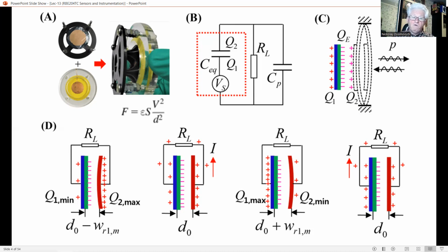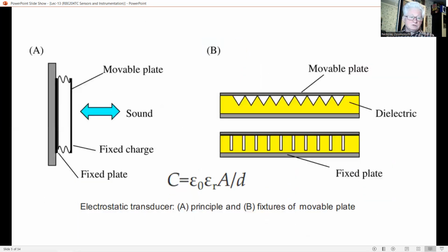Should the plate move linearly proportional to an applied AC voltage to generate the proper sound waves, the capacitor should be biased with a DC voltage higher than the amplitude of the AC voltage. This equation also shows that the sensitivity of the emitter increases with decreasing initial plate distance. To make a robust transducer with a small initial gap and a thin movable plate, as sometimes you might call it, a membrane, the latter is supported not only at its edges but over a large part of the surface, as you can see on figure B, accomplished by a grooved plate or other insulating structures like a grid or net.